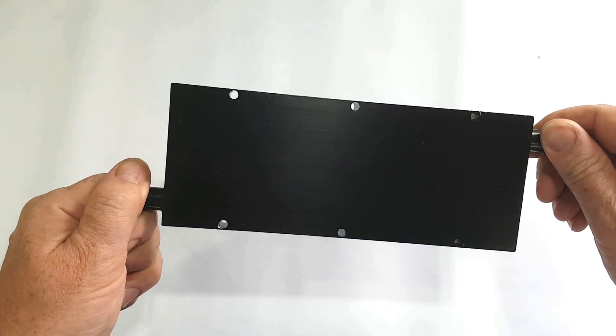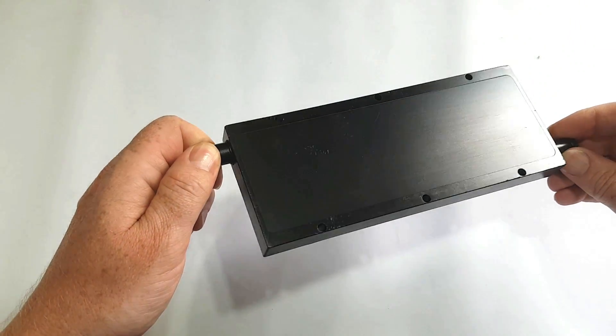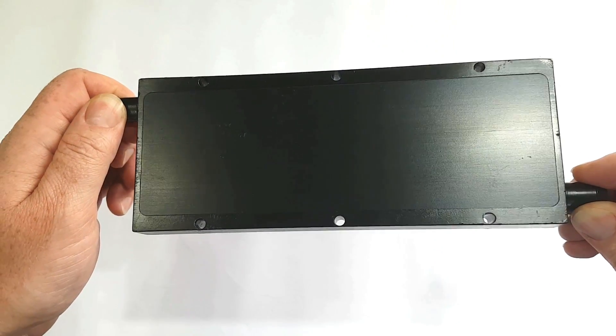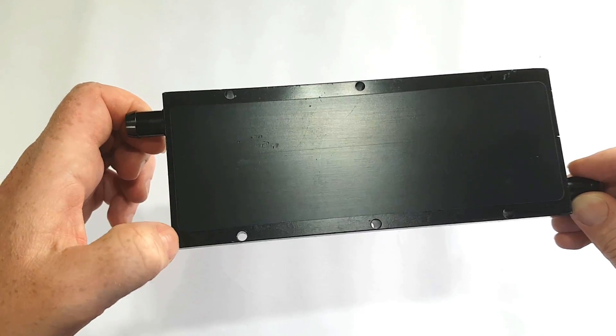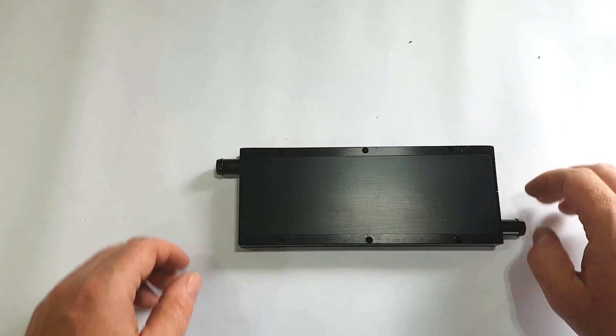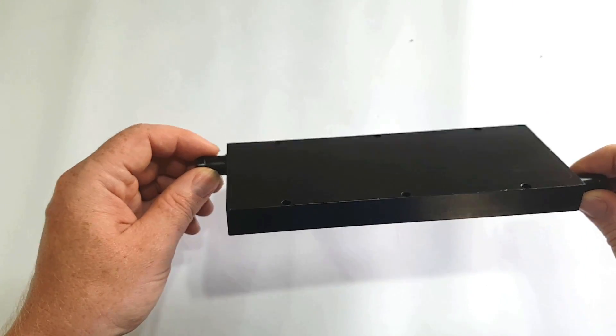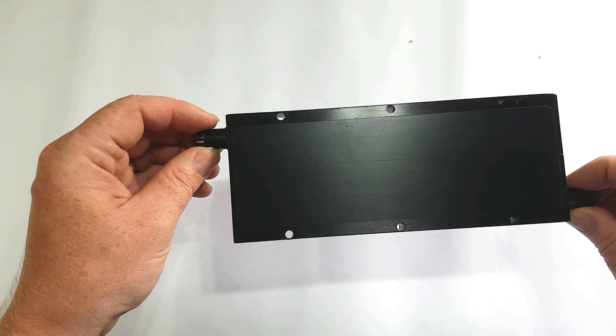You can see this is one piece — there's no seal on it or join. You can actually see the change in light; these have been baked together. So it was one piece — we milled the channels out of here, then we baked on this top part. The advantage of that is there is no join, so it's not going to leak, and it's not going to leak if it gets extremely hot or extremely cold.